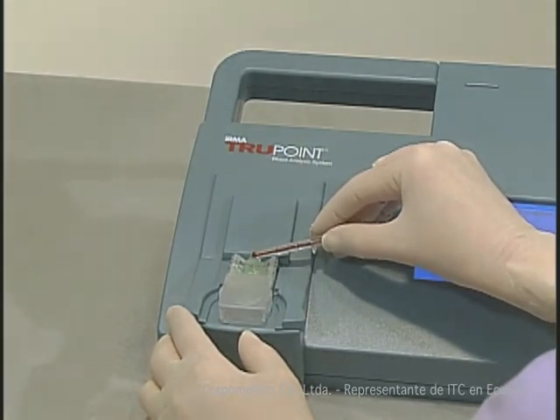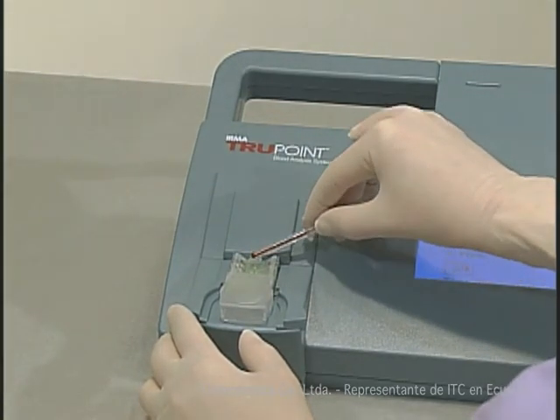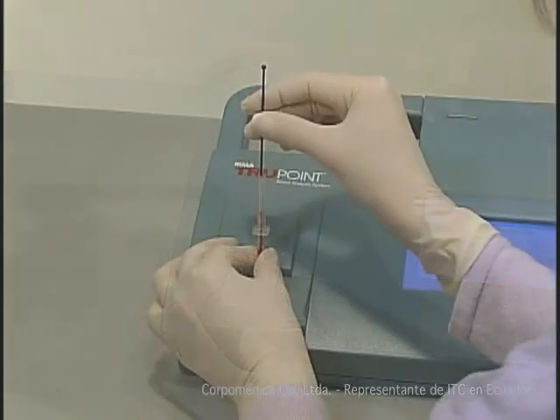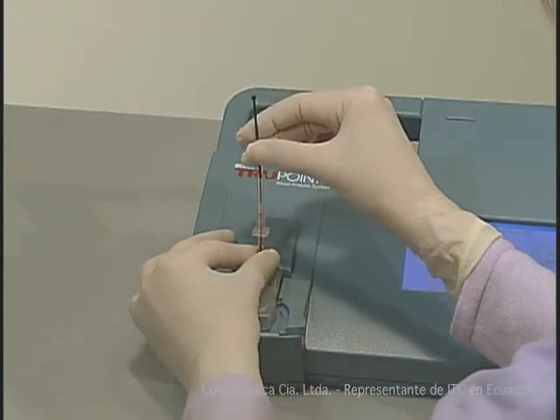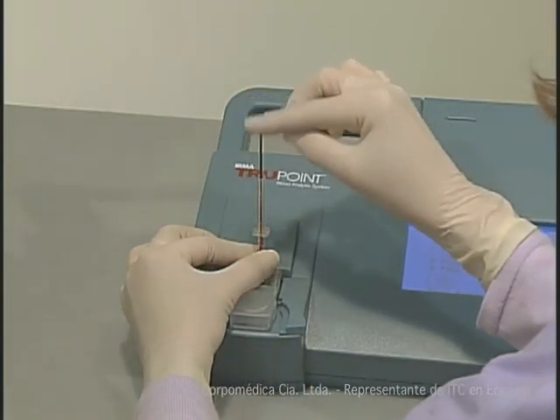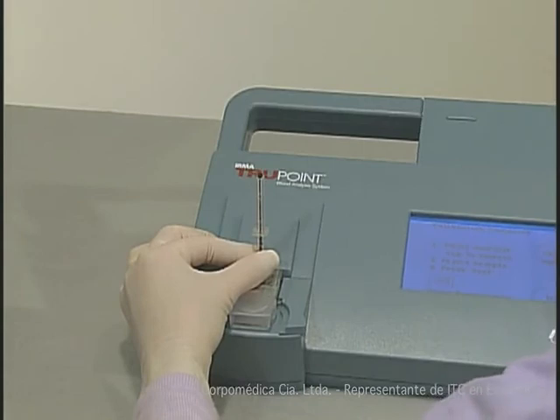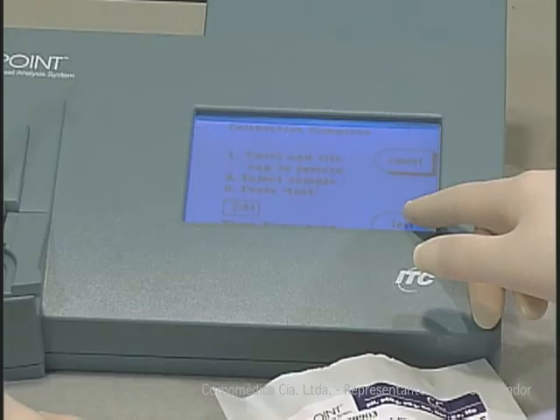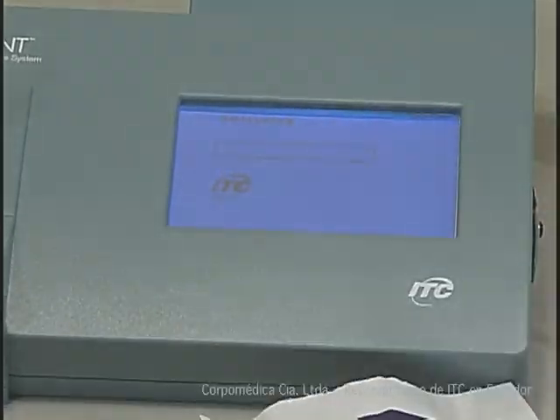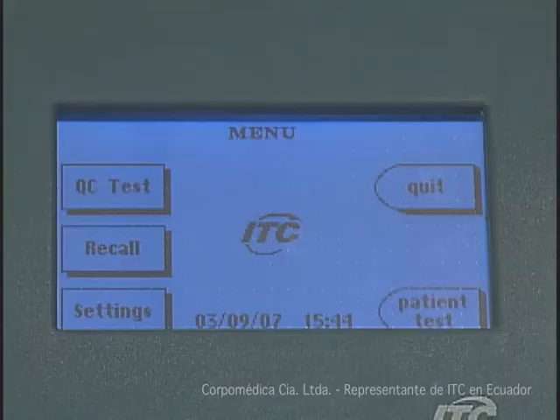Once cartridge calibration is completed, firmly seat the capillary tube tip into the cartridge injection port. Anchor the device with your fingers and insert the black plunger into the capillary tube. Quickly depress the plunger straight down. Verify that there is no calibrant or air bubbles in the sample path, and press Test. Stored patient and quality control test results can be easily looked up by pressing Recall from the main menu.